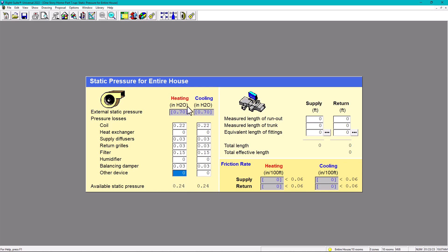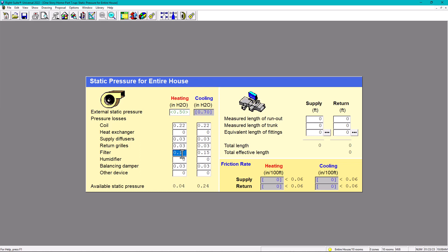But what happens if I put 0.5 instead of 0.7? Let's go to 0.5 - my available static pressure is now only 0.04. And what happens if the customer has cats or dogs, or they don't vacuum frequently and don't change the filter? The filter gets dirty, giving more static pressure at 0.2. Now I have zero available static pressure, which is not good. Or what if a customer needs a high-efficiency filter? At least 0.2 or 0.18 - I don't have any more available static pressure.